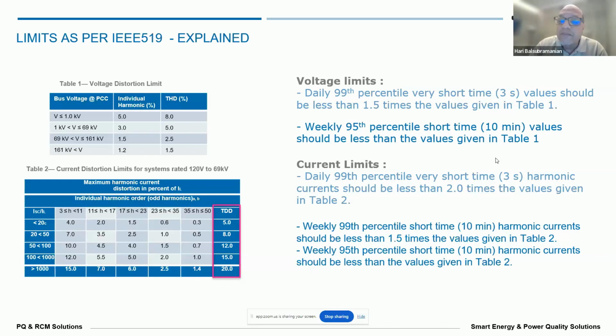So we should find a percentile for that, and then compare it with the table given in the standard. For example, I have shown here the standard for 120 to 69 kV. What are the standards? TDD has multiple limits depending on how your loading is and where you are in the grid.